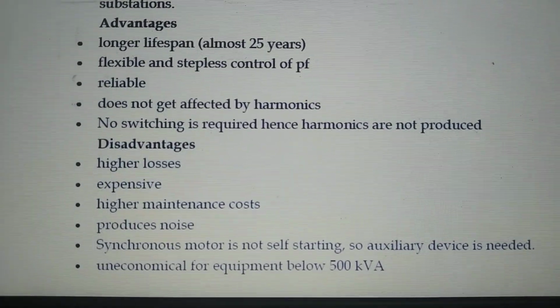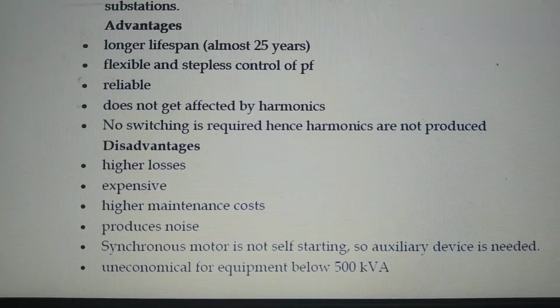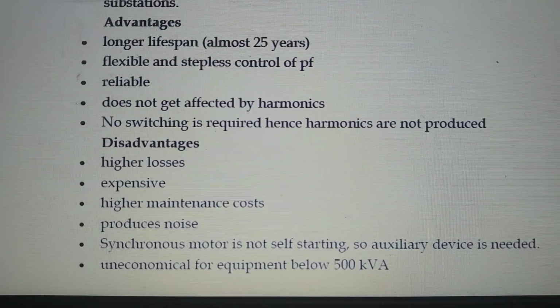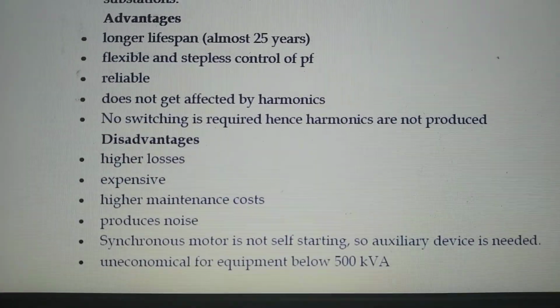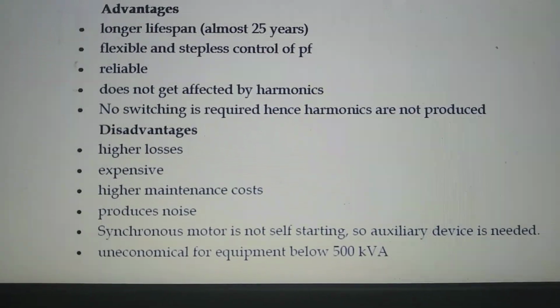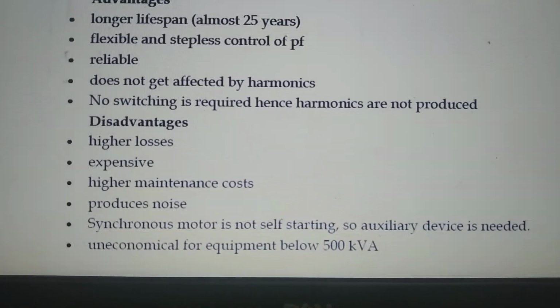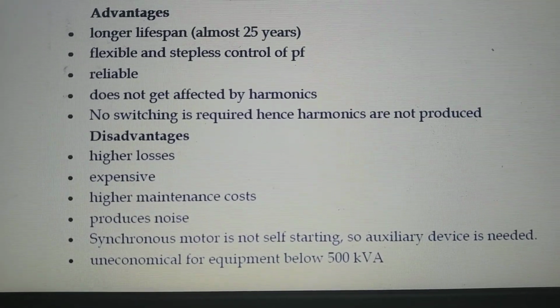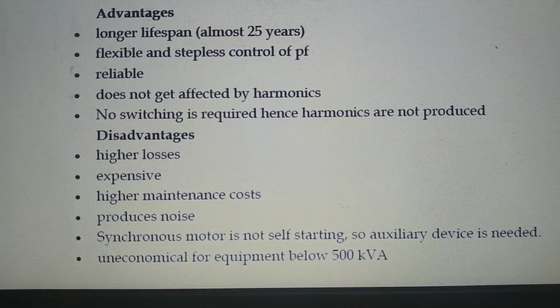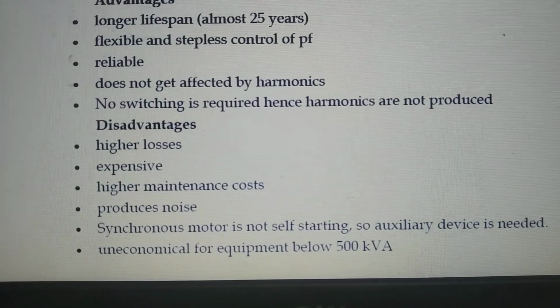The disadvantages are that it is a motor basically, so higher losses take place, and the cost is also more expensive. It needs more maintenance, thereby cost is increased, and because it is a rotating machine it produces noise. A synchronous motor is not self-starting, so an auxiliary device is needed to start the motor. It is uneconomical for equipment below 500 kVA.